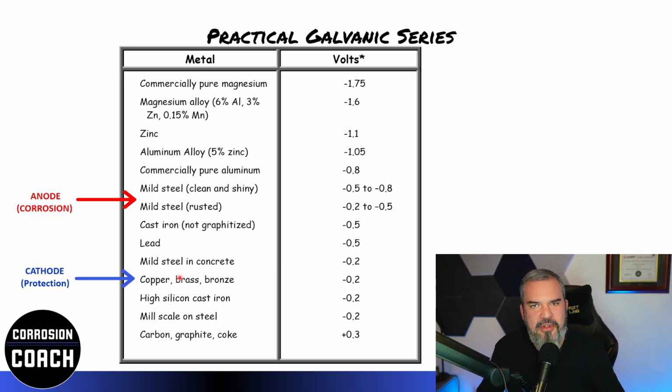Think about those compressor stations. Think about those pump stations. Think about other types of facilities that require grounding to be installed for surges or strikes or anything like that. Typically, they're going to utilize copper as their grounding and even build grounding grids made up of copper for those surge purposes that I just talked about. Well, guess what else is hanging out in those facilities? My carbon steel pipeline. So if we're not careful, we can accidentally or unintentionally damage our steel pipeline or corrode it simply because we have connected it to copper.